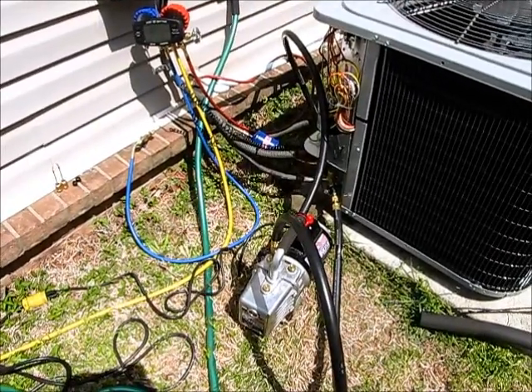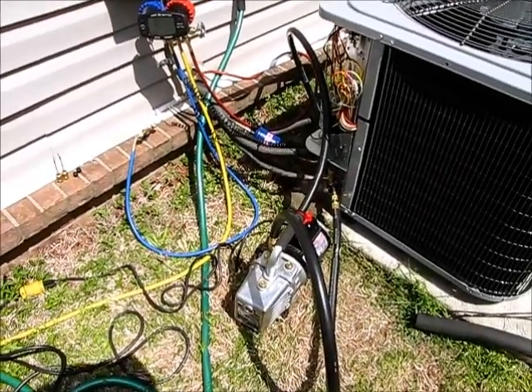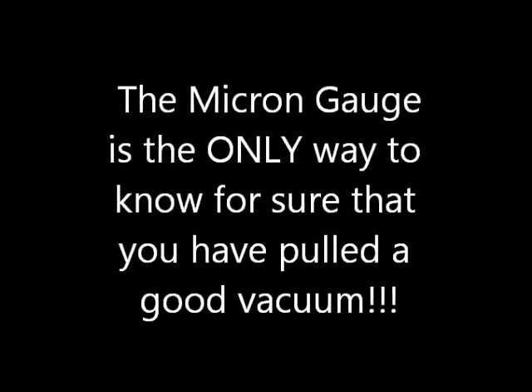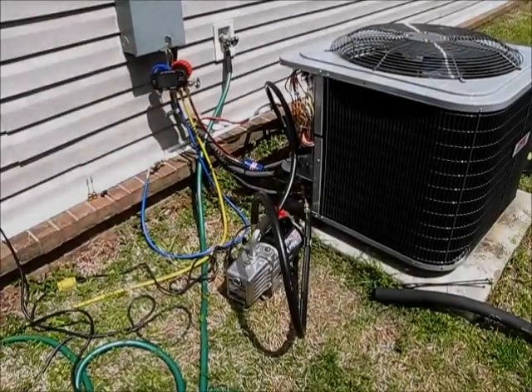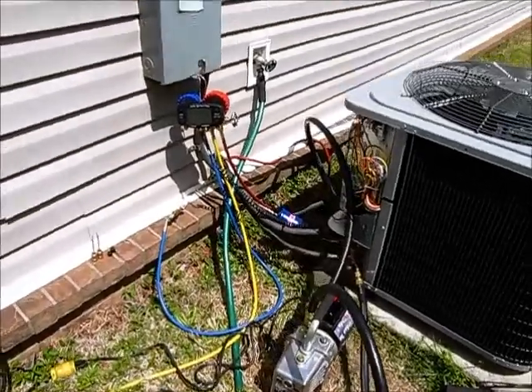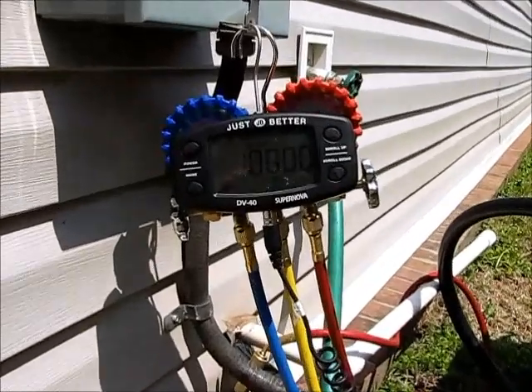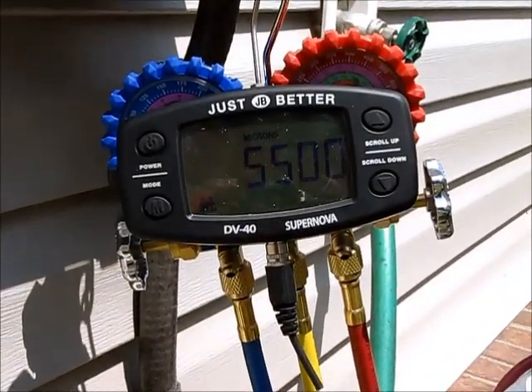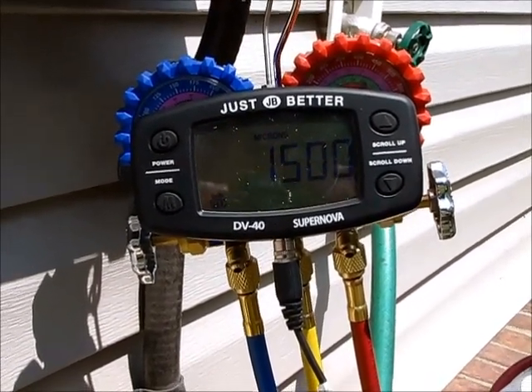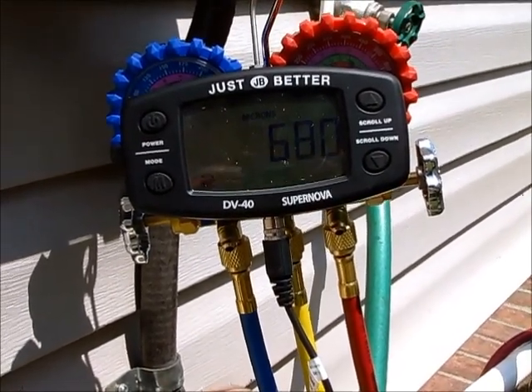We're shooting for 500 microns and as soon as we get there we'll be ready to introduce the freon from the condenser into the system. So right now we are pulling a vacuum. We've just completed our pressure test. This little handy instrument that should be in every installer's vehicle is called a micron gauge.